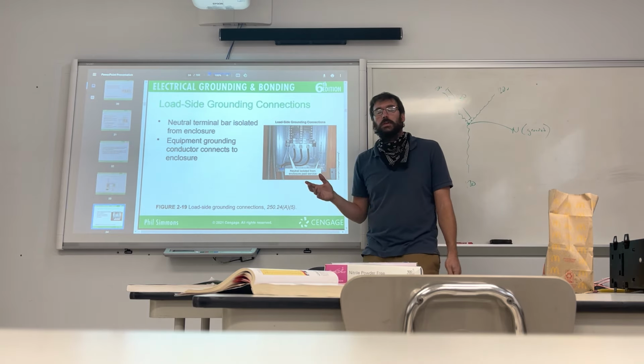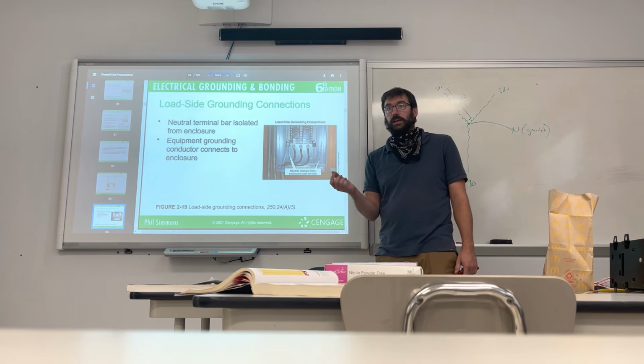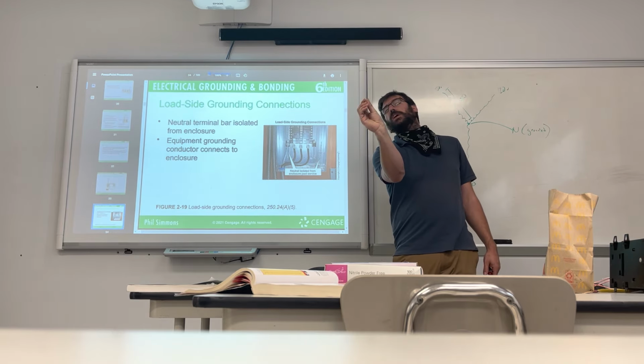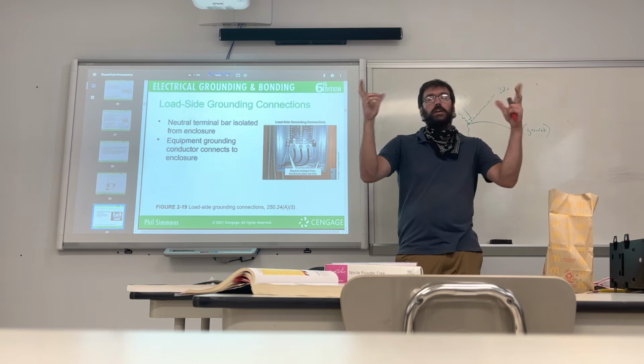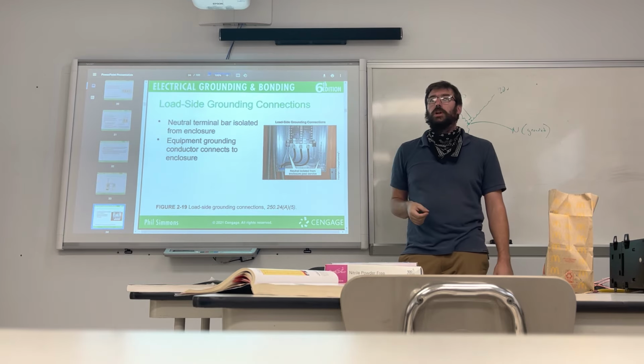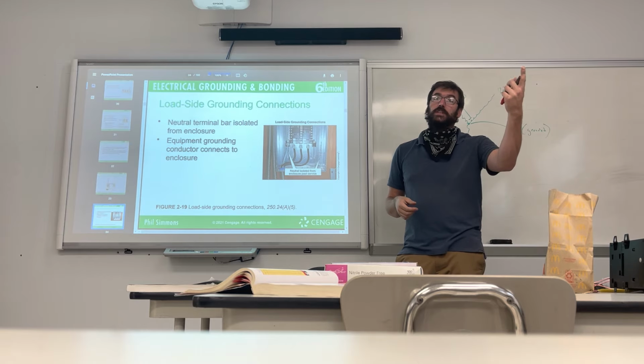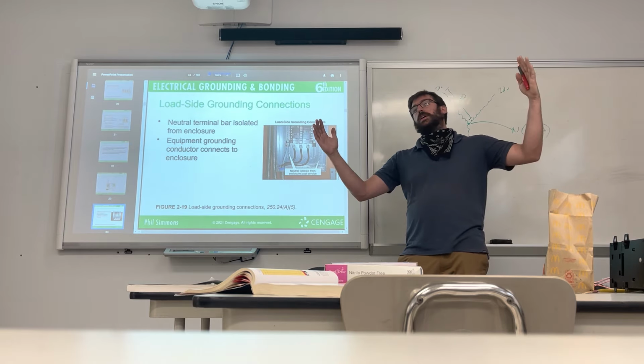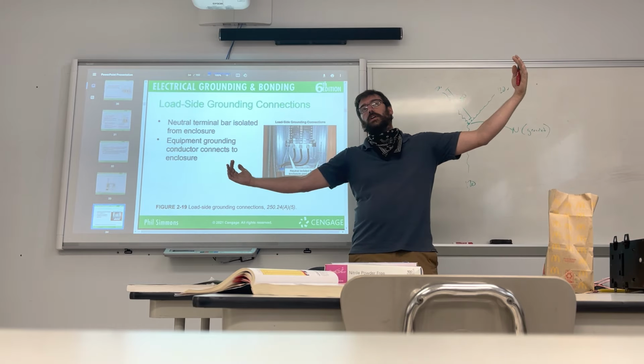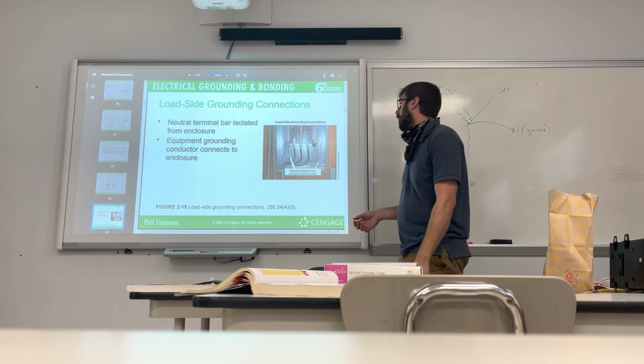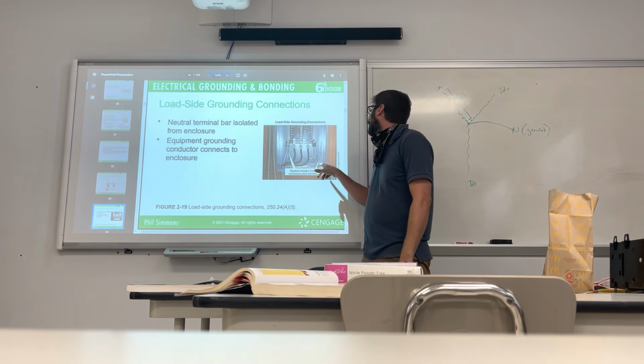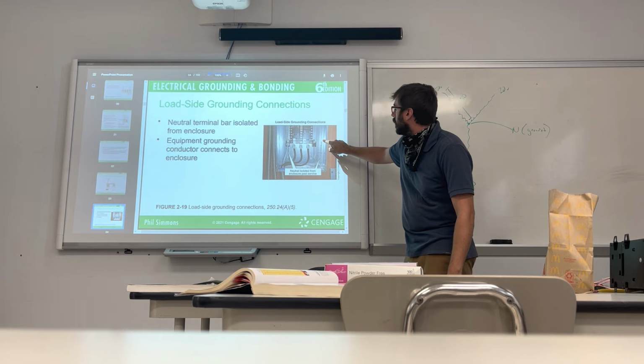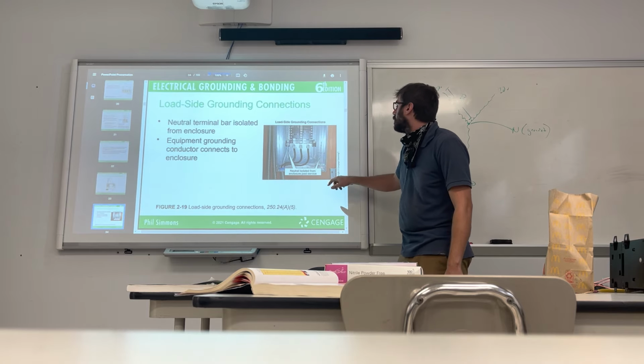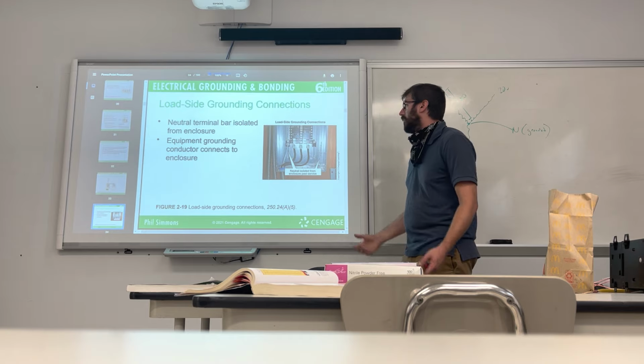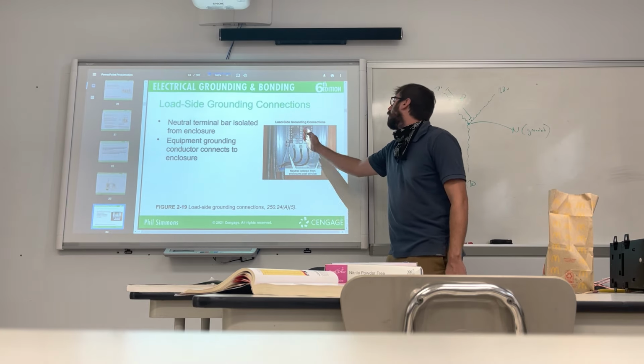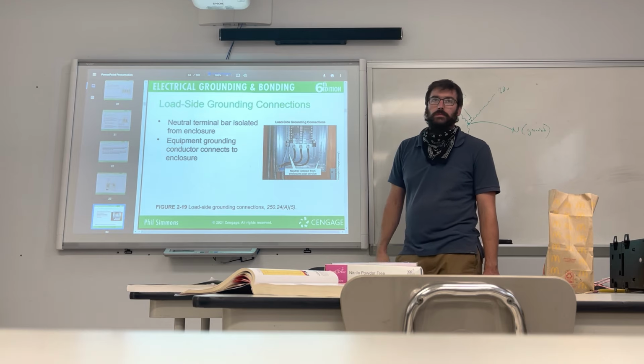And that's all it needs, because with 208 or 480, if that were to arc, the arc gap would only be about an eighth of an inch. Even though it's high voltage, that low of a voltage isn't going to want to arc very far. A 7,000 volt will probably arc, and 13,000 will arc even farther. The higher the volts, the more potential for arcing. So that's isolated from the panel, and the ground is on the lug bar there. So the neutral is isolated from the enclosure, and that's a typical sub panel, which just happens to be a 3-phase sub panel. Okay.